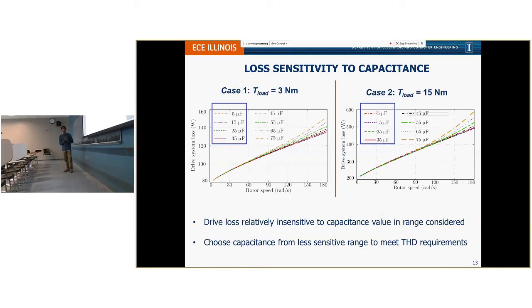But there is one caveat here: how do we choose the value of capacitance, given a range of 5 to 35? This is a certain judgment - you try to use the capacitance which gives the minimum THD, or if the drive's THD is below the standard limits, let's say even for 17 or 18 microfarads, it's still okay. But this is just a judgment, so it can be chosen from anywhere in this range.